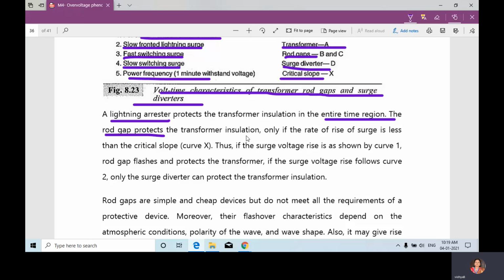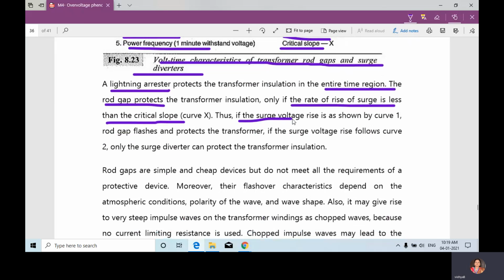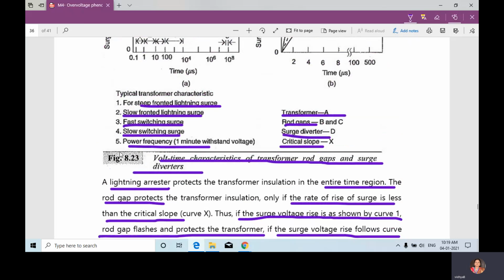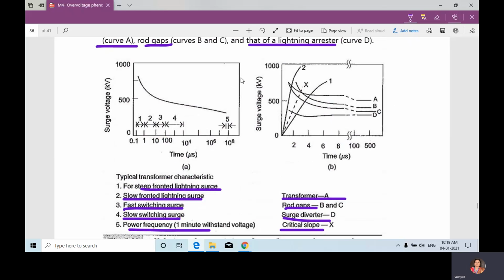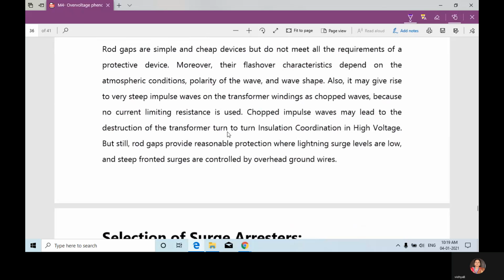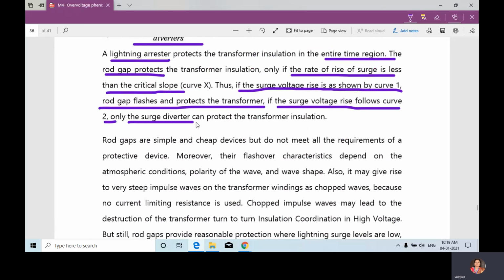only if the rate of rise of surge is less than the critical slope will it protect, and only then will it act. If the surge voltage rise is as shown by curve 1, the rod gap flashes and protects the transformer. If the surge voltage rise follows curve 2, you can observe that only then can the surge diverter protect the transformer insulation.